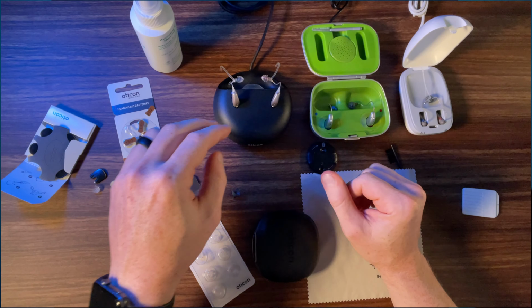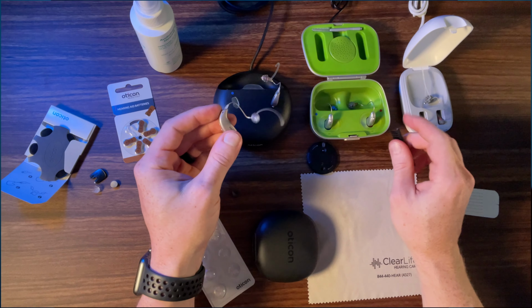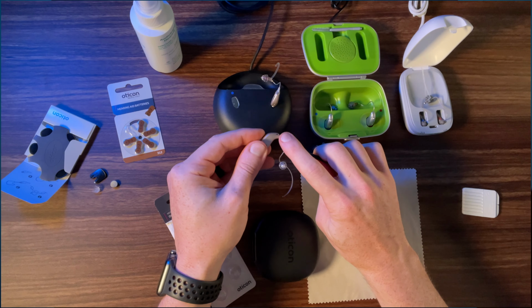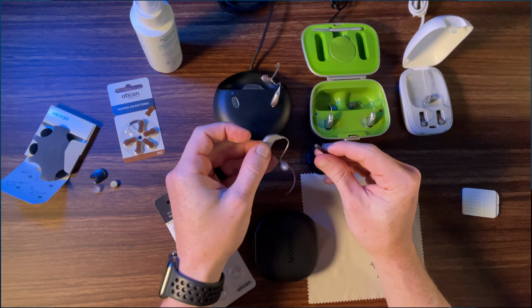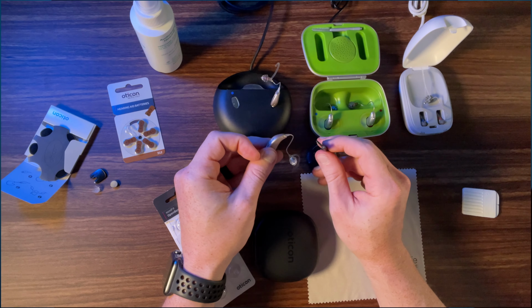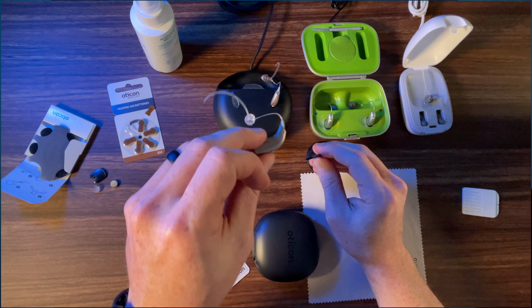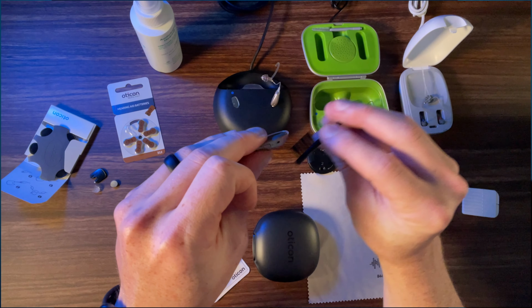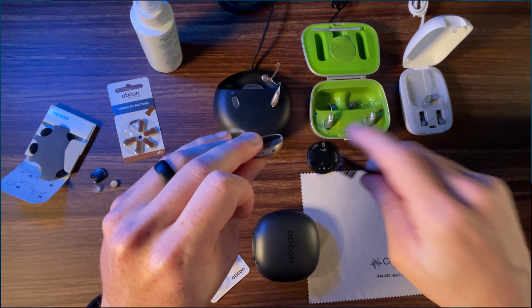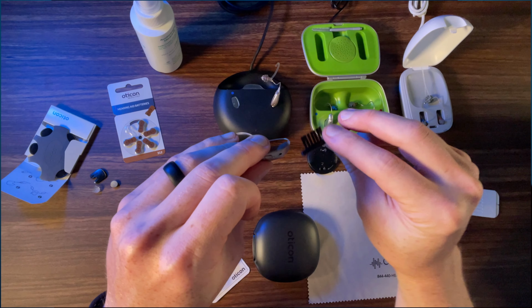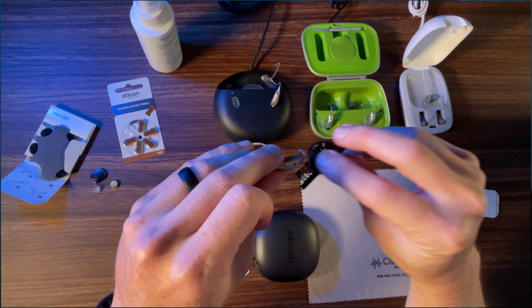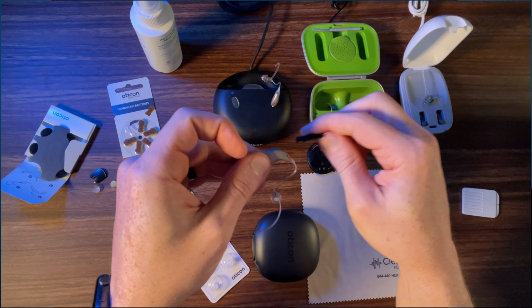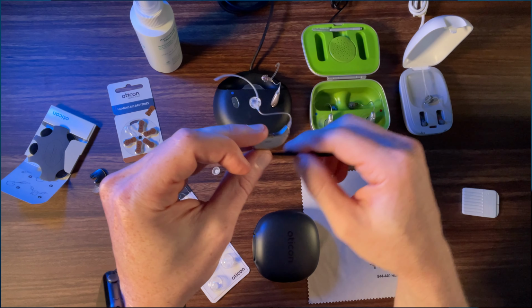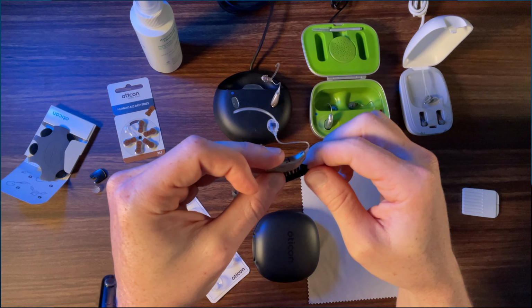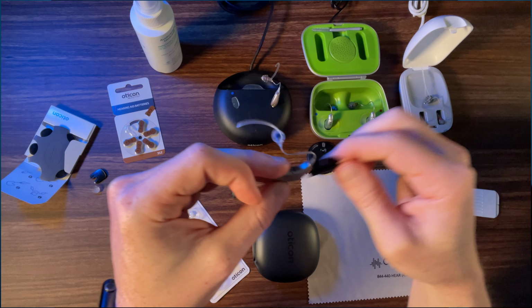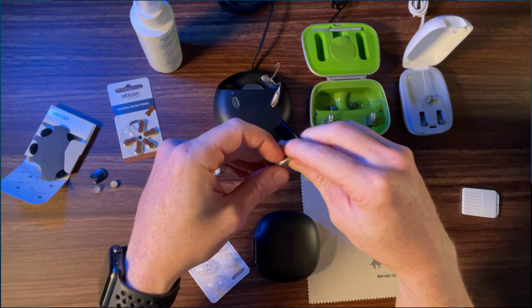Okay, and then generally speaking, a couple of other issues that can come up. You can get debris stuck inside the microphones. So if you start to notice that devices sound weak, you want to point the microphone down, and you want to brush along the microphone with the microphone facing down. That way any debris won't fall deeper into the body of the hearing aid. Instead, it will just fall out of the bottom of the hearing aid. You would be surprised how big of a difference it makes having clean microphone ports.